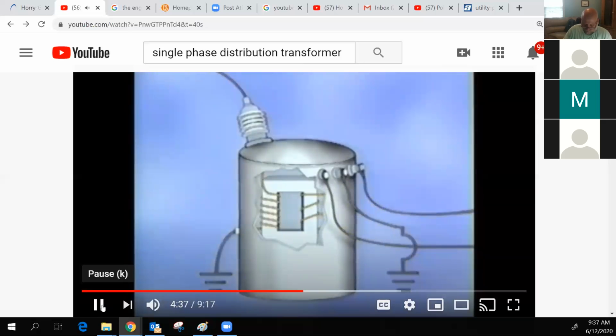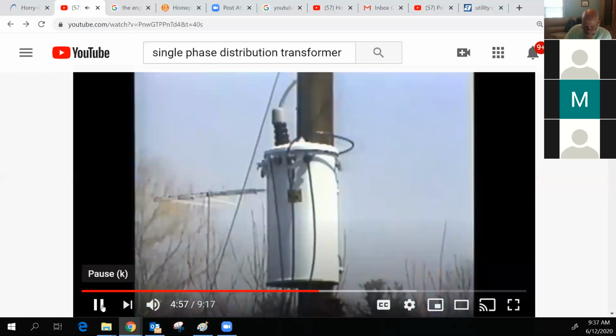In this example, the lead passing through the middle bushing on the secondary side is grounded. The leads on either side are hot. The secondary leads are usually connected to wires that form a secondary bus, which supplies consumers with electricity through service drops. Here's a typical pole-top transformer. Let's identify the elements that allow you to recognize this component as a transformer. First, it has a large primary bushing on top, connected to a distribution line. Second, smaller secondary bushings are located on the side of the housing.